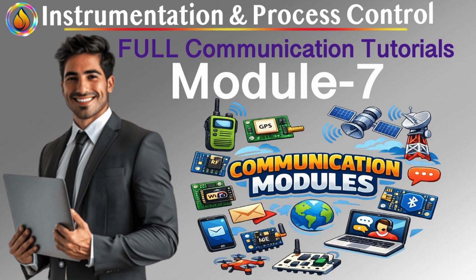Why this matters more than speed. Let me be very direct. Foundation Fieldbus does not win by being fast. It wins by being predictable. Every device knows when it will speak, when it must be silent, and when data will arrive. That certainty is what allows control loops to execute in the field, multiple vendors to interoperate, power and communication to coexist, and long segments to remain stable.